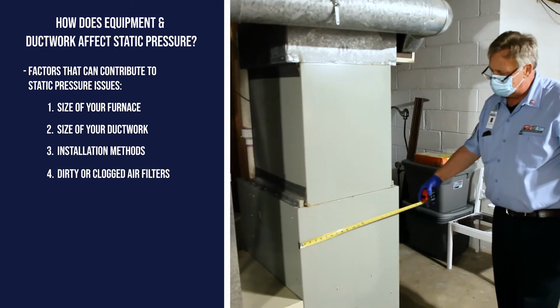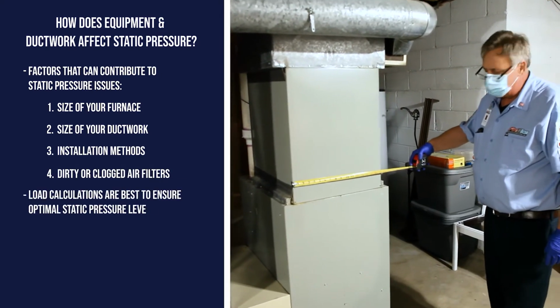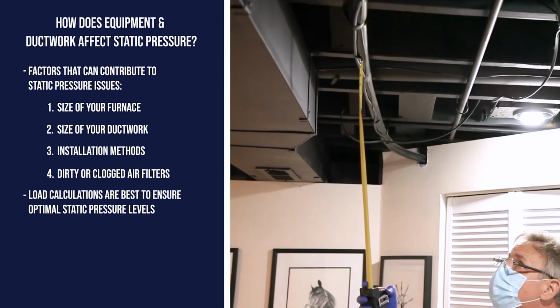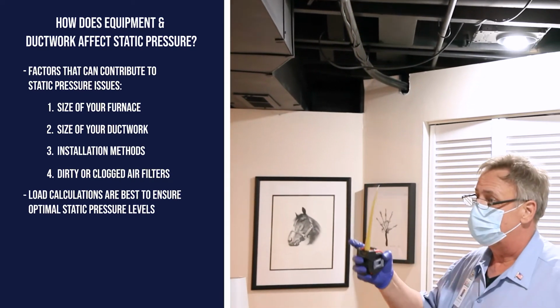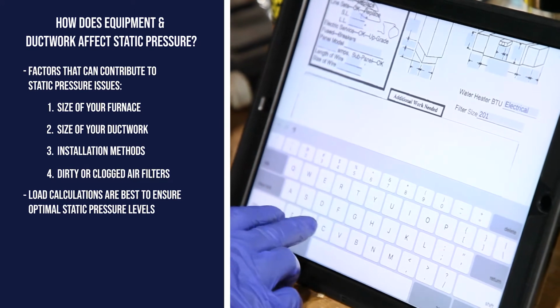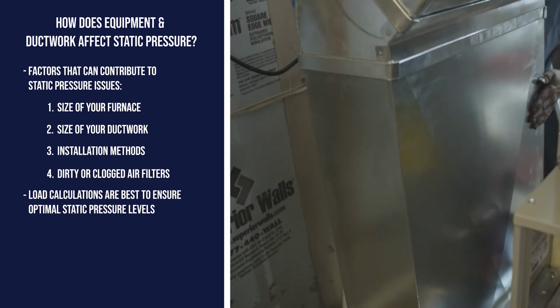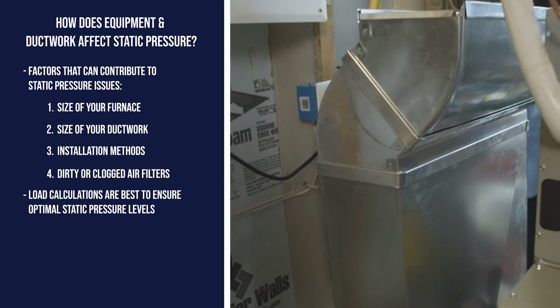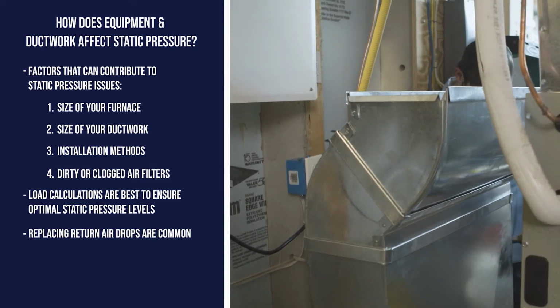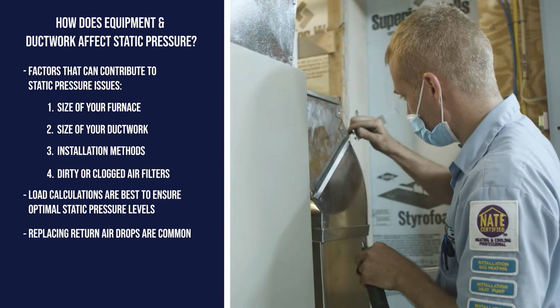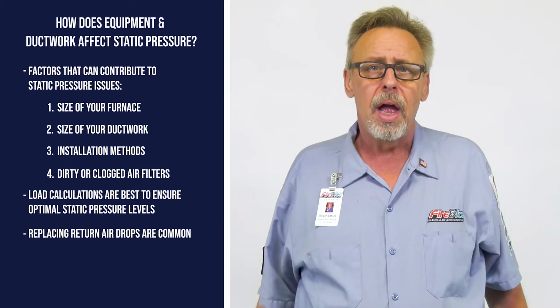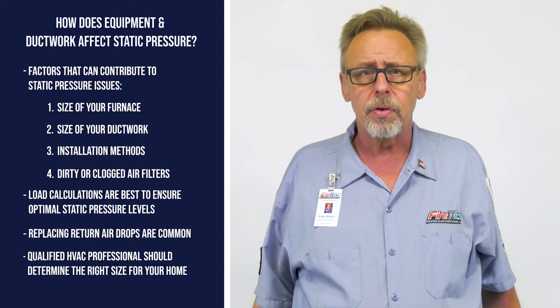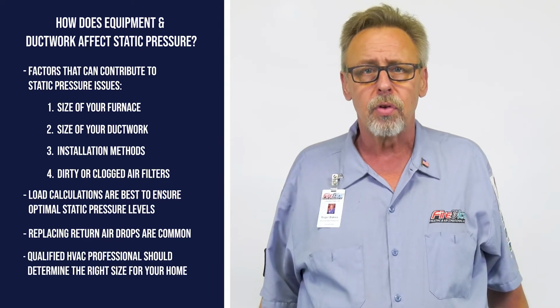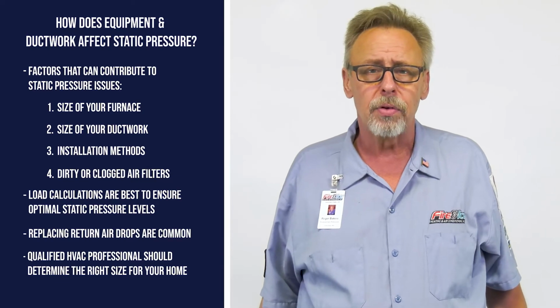The best way to maintain optimal static pressure levels is to have load calculations performed to determine the correct size system for your home and to determine any modifications that your ductwork may need. In fact, a lot of the estimates we provide here in Central Ohio include the replacement of return air drops because past HVAC systems were undersized. Having a qualified HVAC professional determine the right size for your home is critical in maintaining optimal static pressure levels.